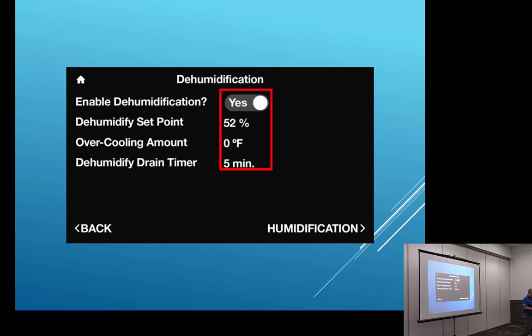I don't think the low stage. No, high stage. But we're not selling them as dehumidifiers. They're sold as energy efficiency. People watching commercials get misconstrued that dehumidification is part of it, and it really isn't. It's all about energy efficiency. So we really dehumidify better at the higher stages than the lower stages, but they're designed to run longer on lower stage because of energy efficiency. So just keep that in mind when you're out there looking at replacing that old system.